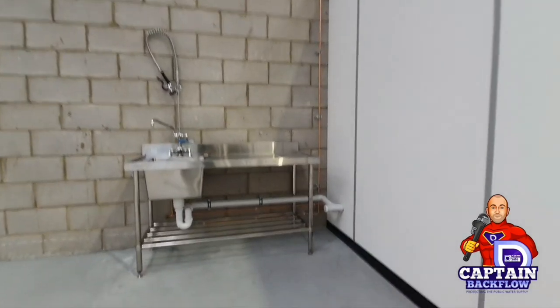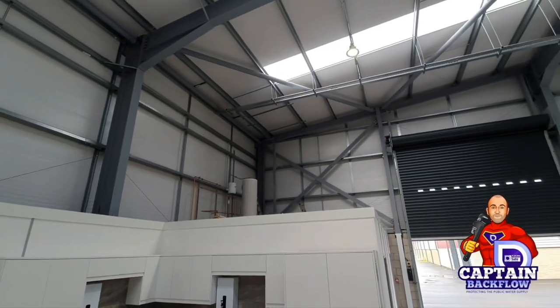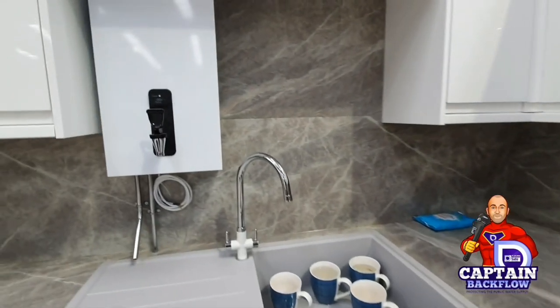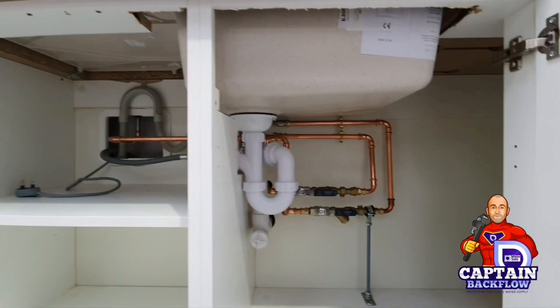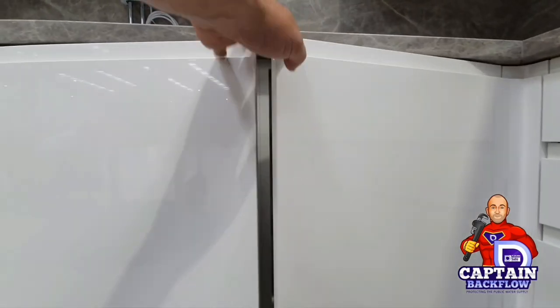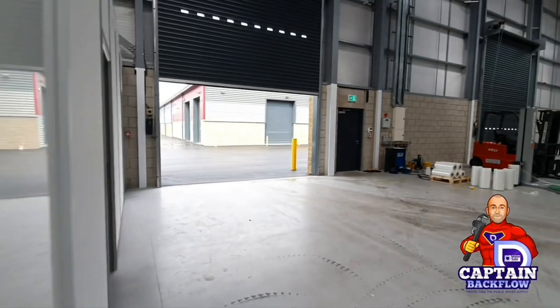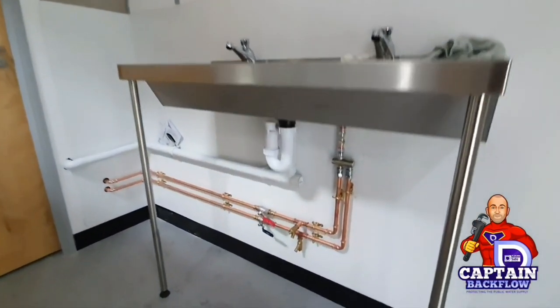The part washing sink — that was supposed to be three but due to cost and availability one was opted for and it's sufficient. It's got a pull-down on it and a UK AUK3 air gap on the tap. In the kitchen area you can just see the water heater that's been installed. We've got two over-sink water heaters — they only require single check valves but we've fitted doubles because we can fit a double with isolation. The washing machine has got a double check valve with isolation. The taps themselves have got singles because it's a mixer tap. The taps from Howden's got replaced because I'd asked them to confirm the taps were WRAS approved and they couldn't — I also asked if they could meet Schedule 4 of the Water Supply Water Fittings Regulations and they couldn't.